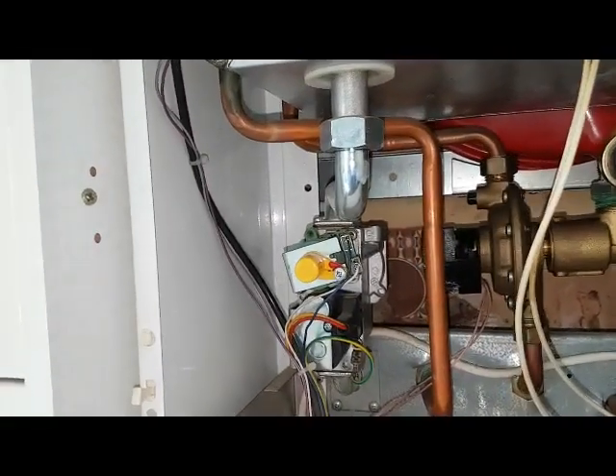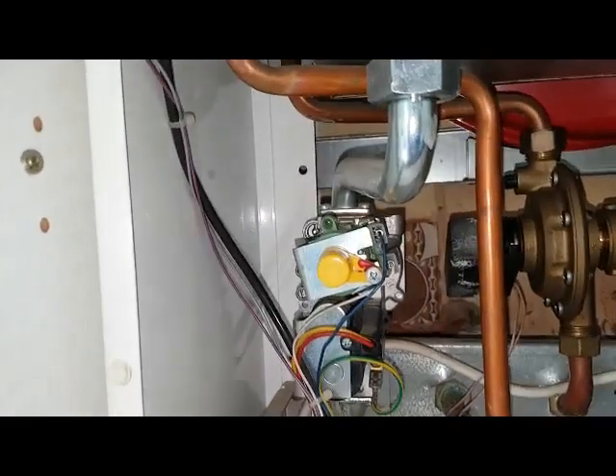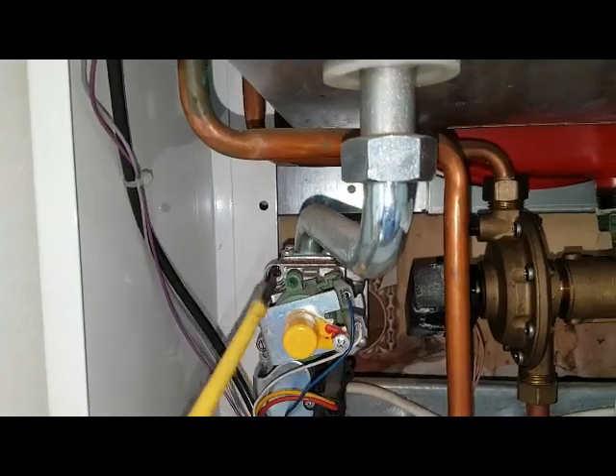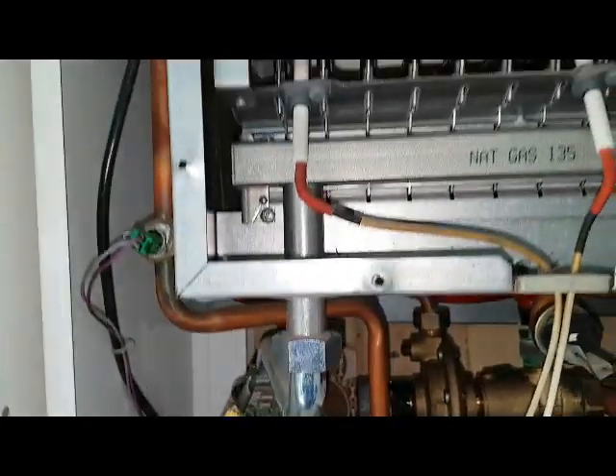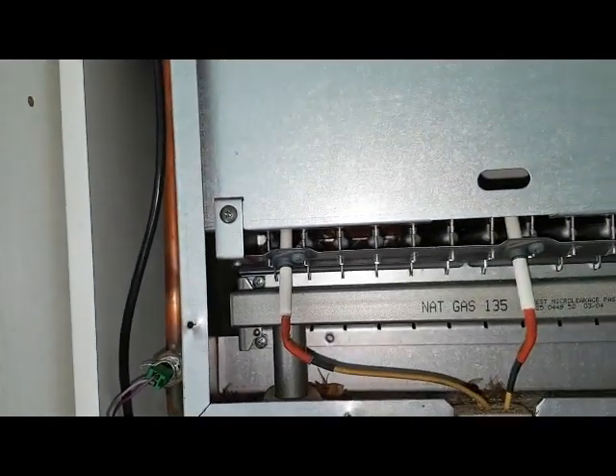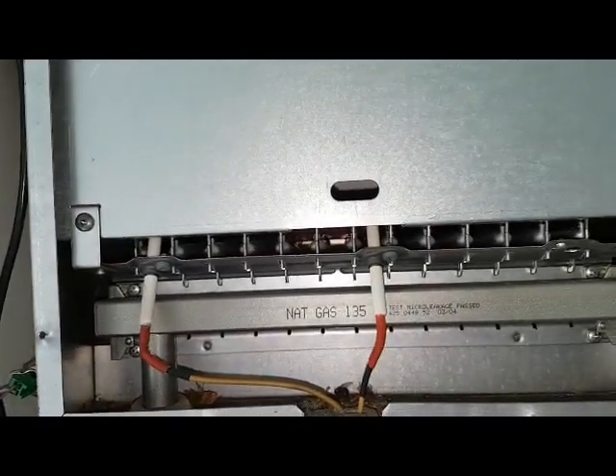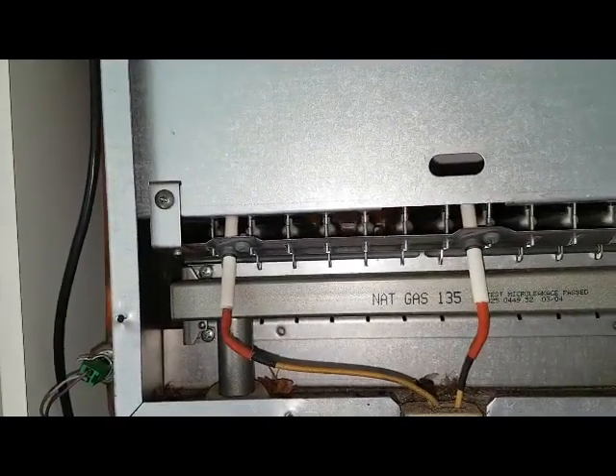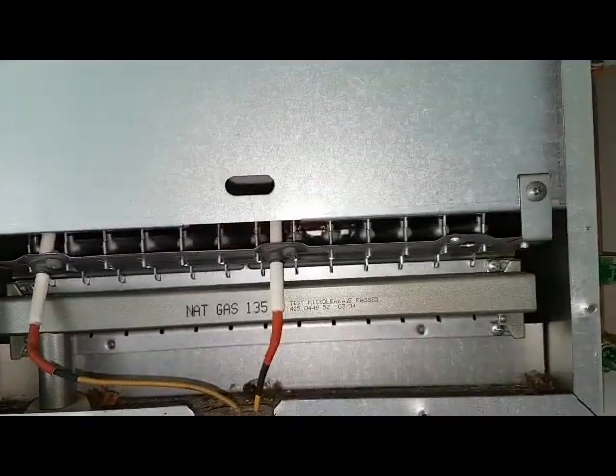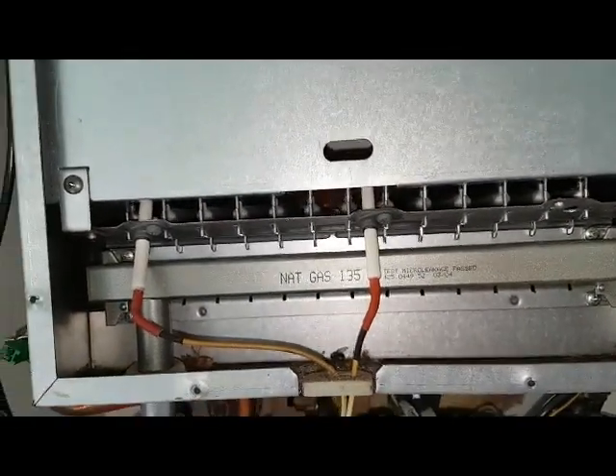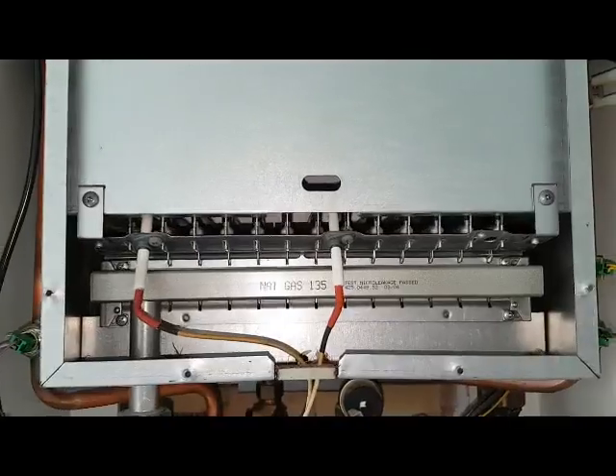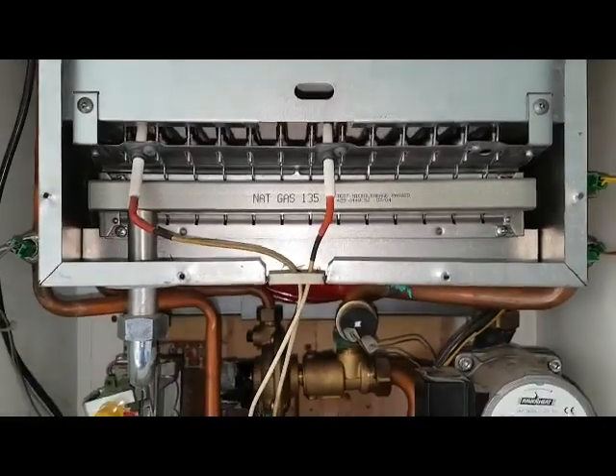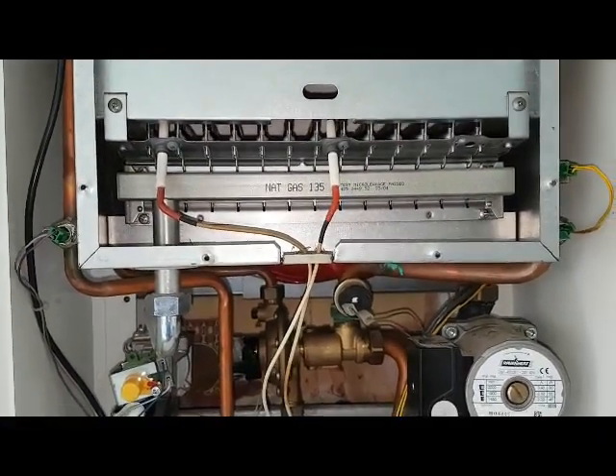Also, the gas valve will open, that will release gas through this pipe up into the burner through the jets. The burner will light on a low flame initially, and then it'll modulate up to whatever it's set at. So the burner will be on, and that's your central heating operation.